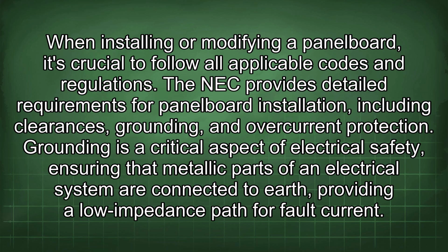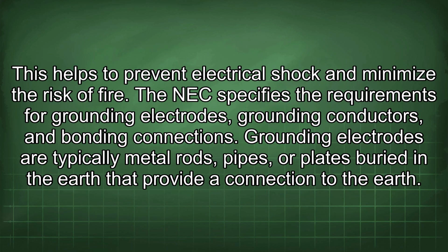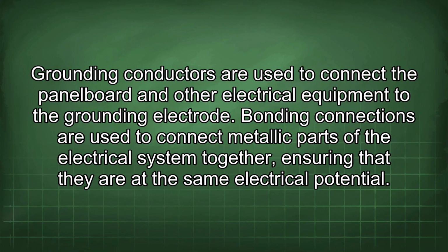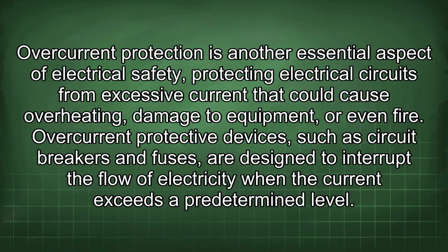Grounding is a critical aspect of electrical safety, ensuring that metallic parts of an electrical system are connected to earth, providing a low impedance path for fault current. This helps to prevent electrical shock and minimize the risk of fire. The NEC specifies the requirements for grounding electrodes, grounding conductors, and bonding connections. Grounding electrodes are typically metal rods, pipes, or plates buried in the earth that provide a connection to the earth. Grounding conductors are used to connect the panel board and other electrical equipment to the grounding electrode. Bonding connections are used to connect metallic parts of the electrical system together, ensuring that they are at the same electrical potential.